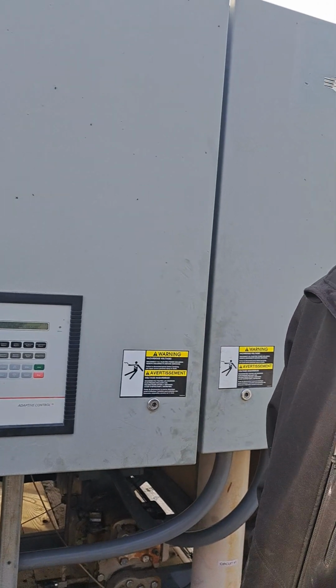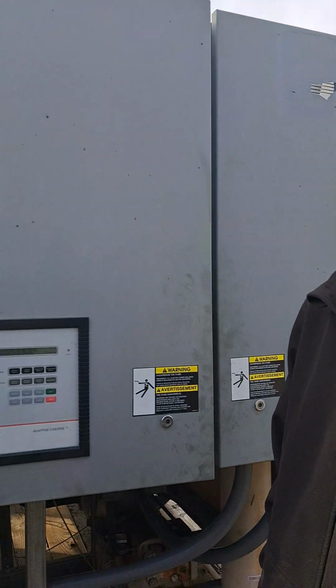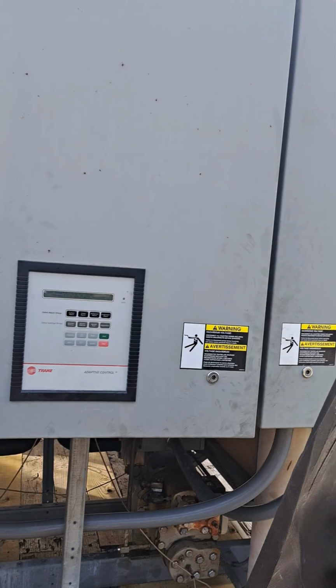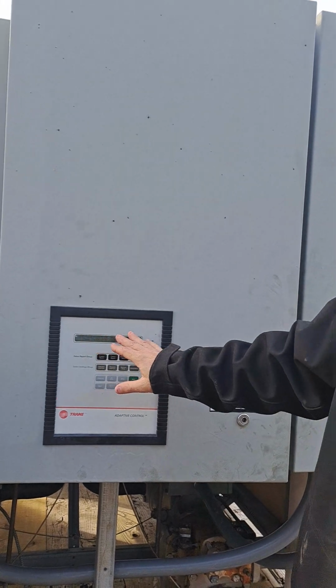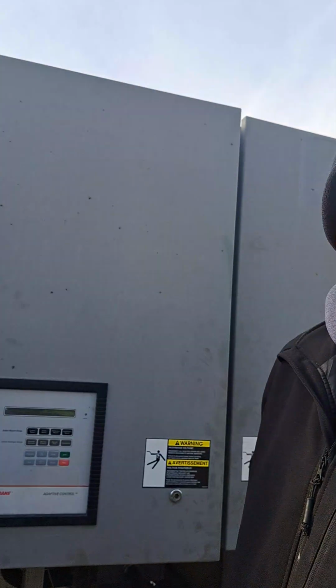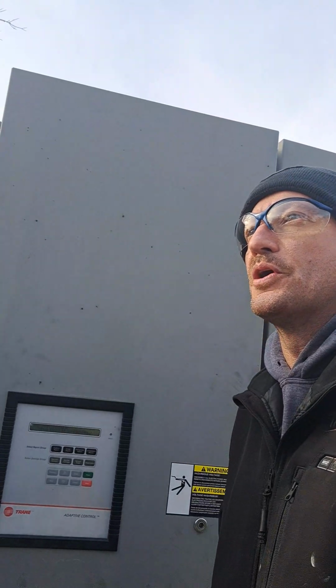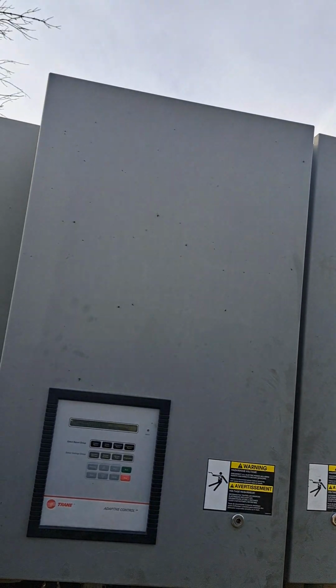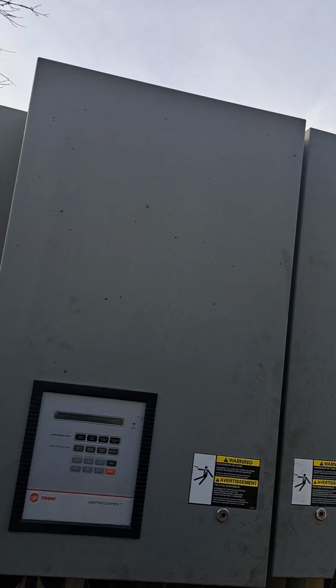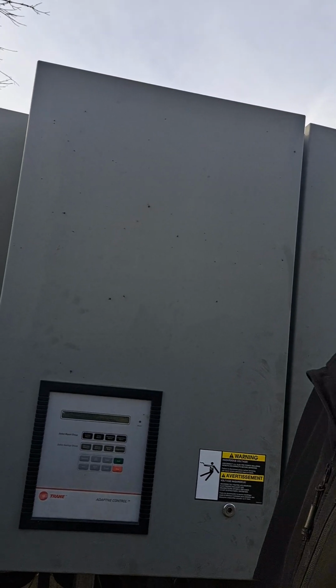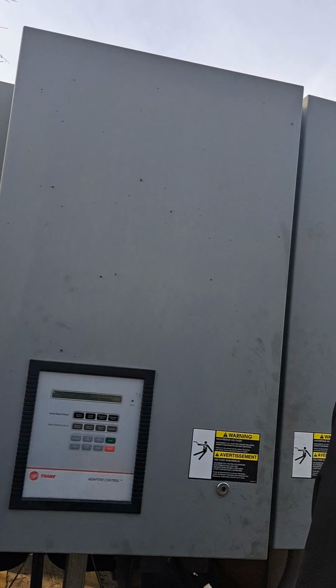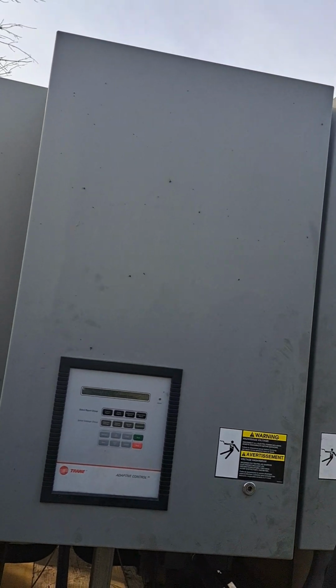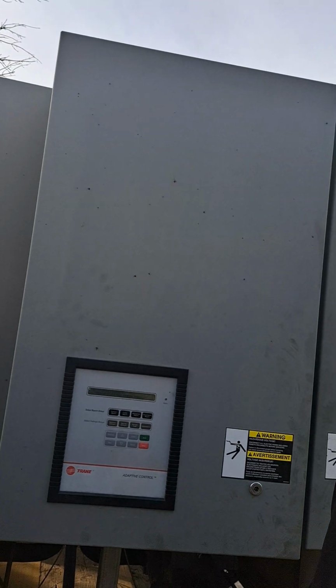So our set point is our return from the floor. Return from the floor. Yeah. Okay. Gotcha. If you need to change that, that's where it's at. You probably won't. I mean, you might decide, hey, we need to harden the ice up a little bit or whatever. That's what I was going to say. How will we know? I mean, with outdoor rinks, you can't really do that. Yeah, I've been through that a bit, so we'll know the difference for hockey and figure skating, the different set points they like, and outdoors you really can't do that. Yeah. So indoor, you can harden the ice up a little bit by turning it down, make it a little bit softer, for the different skating.